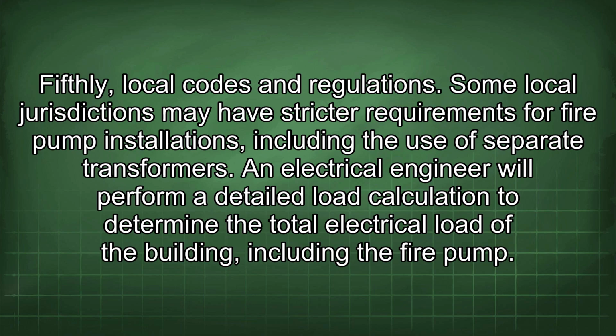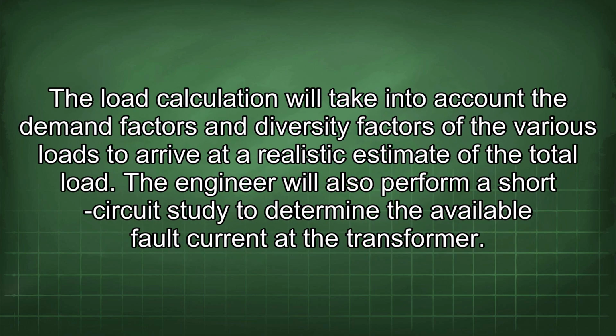An electrical engineer will perform a detailed load calculation to determine the total electrical load of the building, including the fire pump. The load calculation will take into account the demand factors and diversity factors of the various loads to arrive at a realistic estimate of the total load. The engineer will also perform a short-circuit study to determine the available fault current at the transformer.